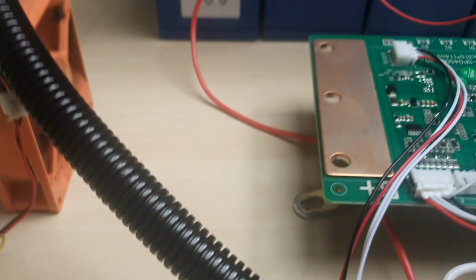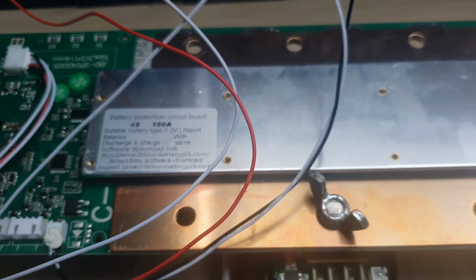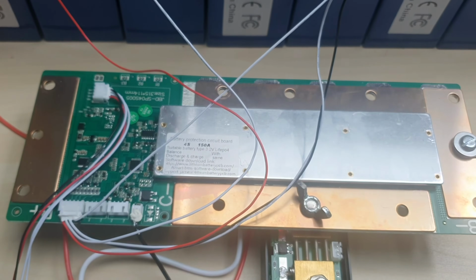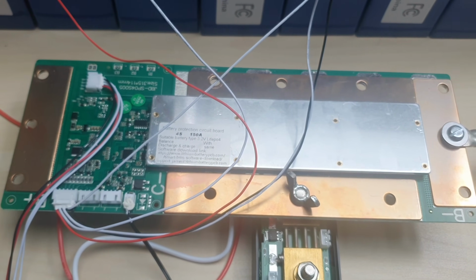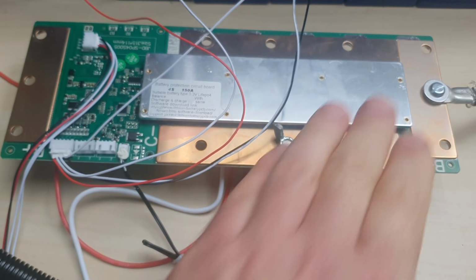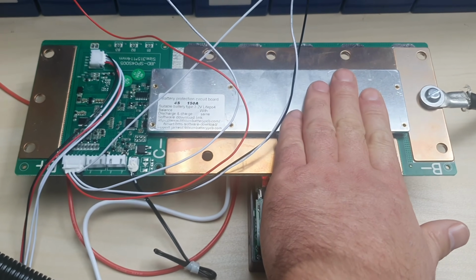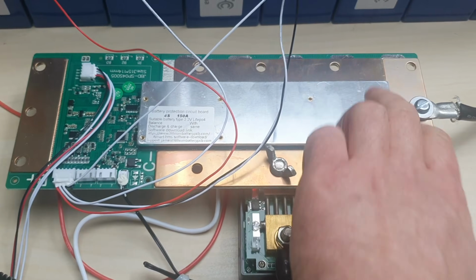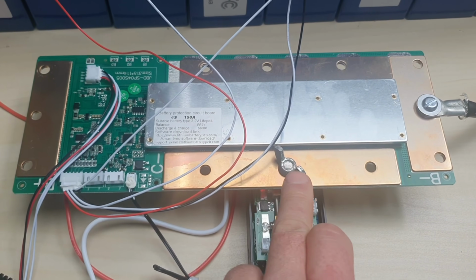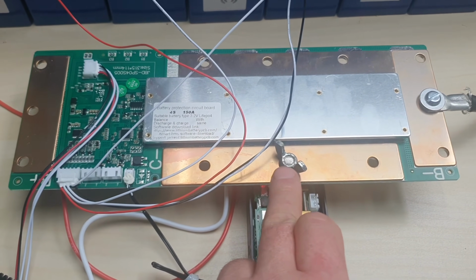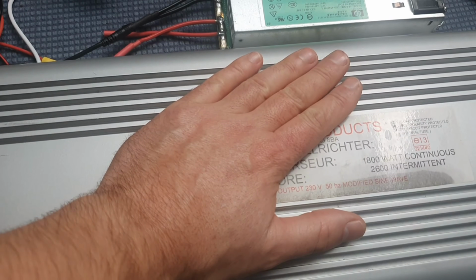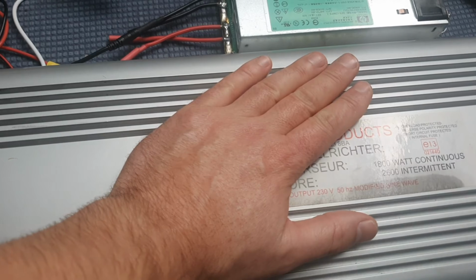I've had to jerry rig up a fan to cool the BMS because it was getting exceptionally hot. According to the software, it was getting up to about 67 degrees, and literally you could feel the heat. I mean, it is hot. I can leave my hand on it now. This bolt connection is exceptionally hot, but there's 130 amps running through that single bolt connection there. The inverter's warm, but again I can keep my hand on it. The fan is running on it.